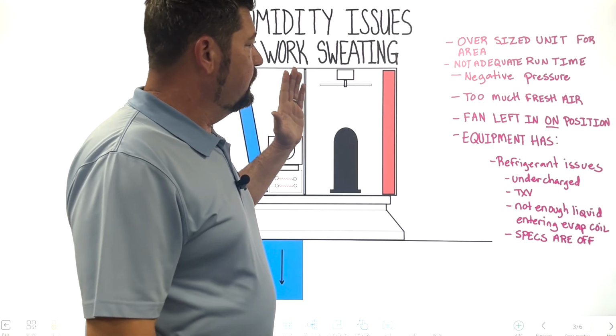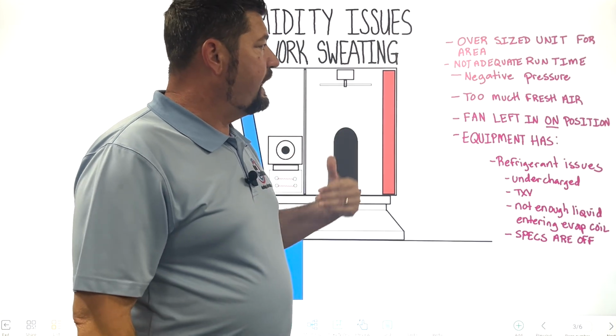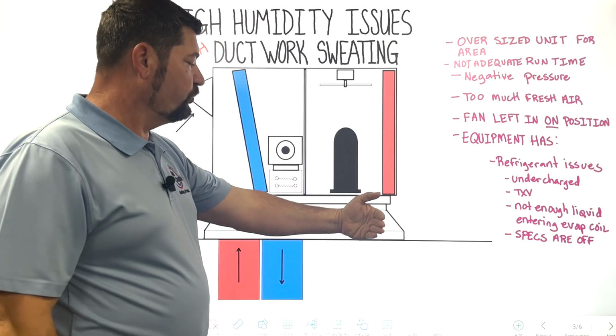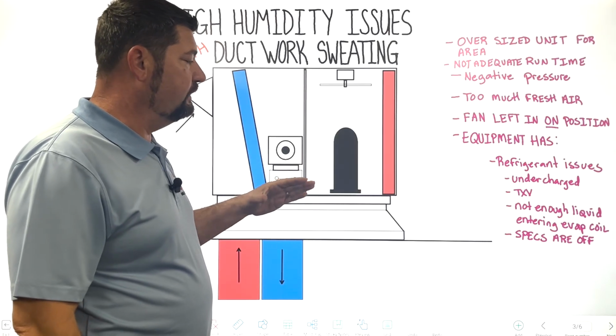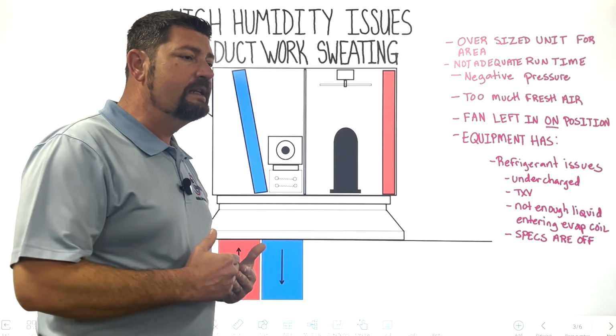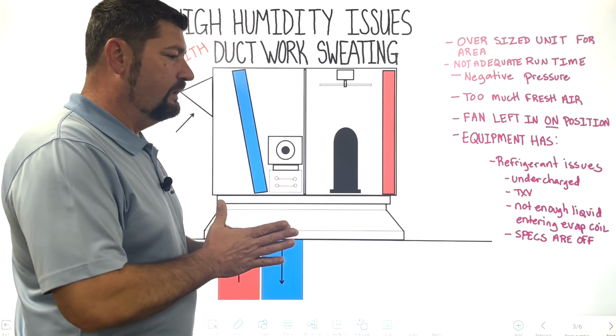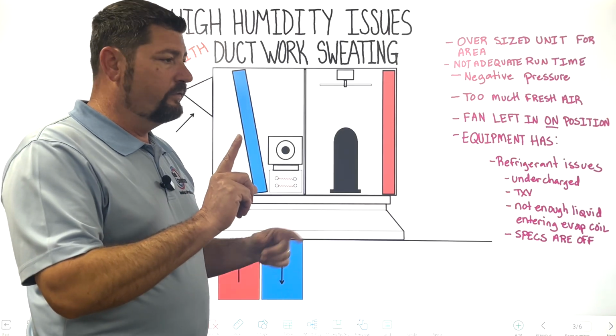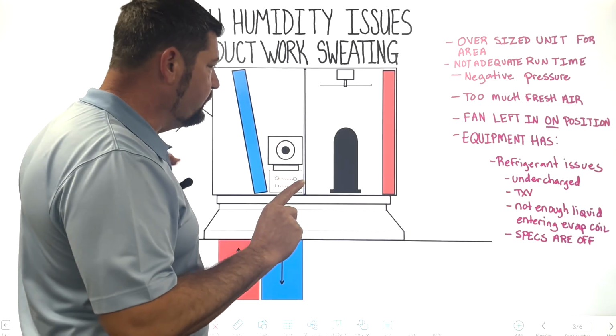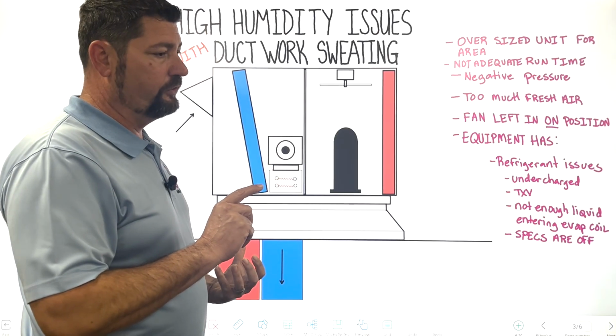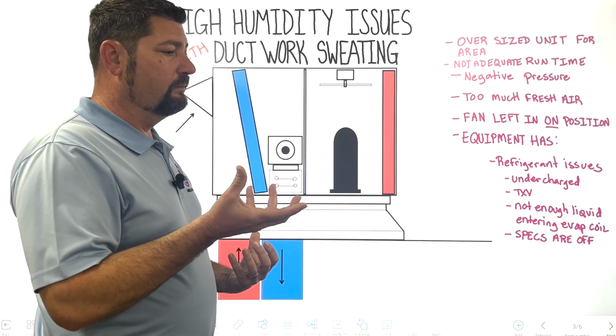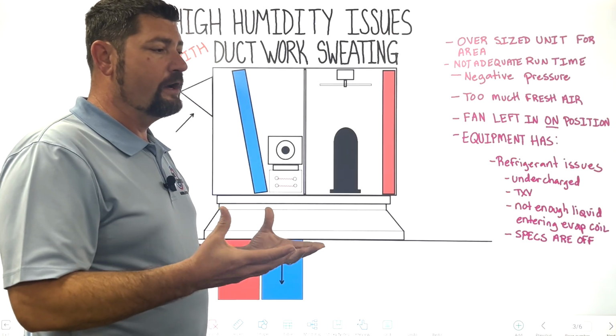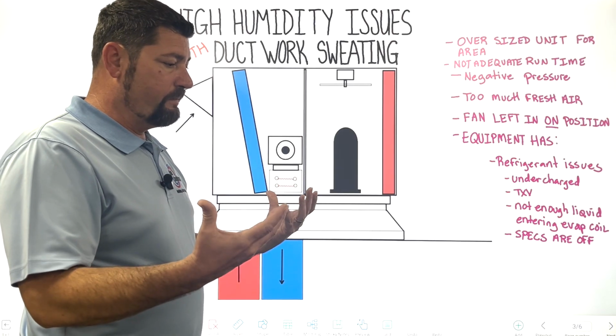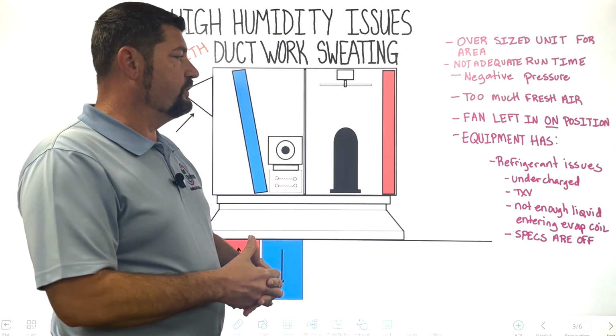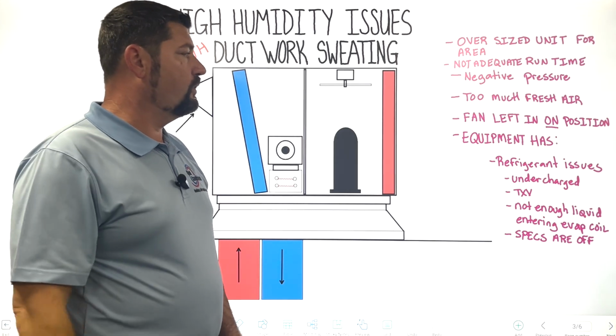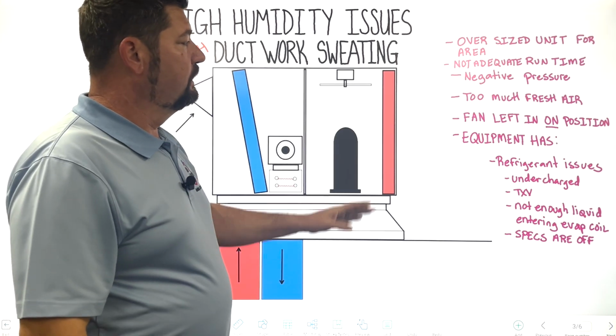And so not enough run time, or not adequate run time, will shorten the cycle that it's running, and that's not going to allow enough humidity to leave the area. And that's kind of like step one of the problem. Step two of the problem would be if there is a negative pressure on the structure, then that humidity is only going to grow to a higher amount, and it's going to eventually reach dew point as the temperature starts to fall based on your cooling demand.